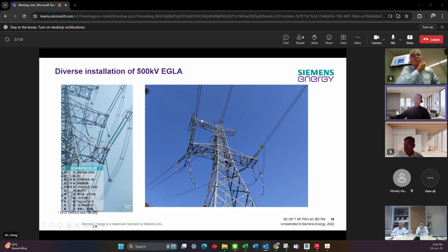Therefore in China, we have such a design with a flexibly connected surge arrester and a long rod insulator as a gap holder. Because the gap must be stable. The gap means if you have a stable gap distance, then the working condition of each sparkover will also be constant, will not be variable. It is guaranteed for the working condition of the EGLA.